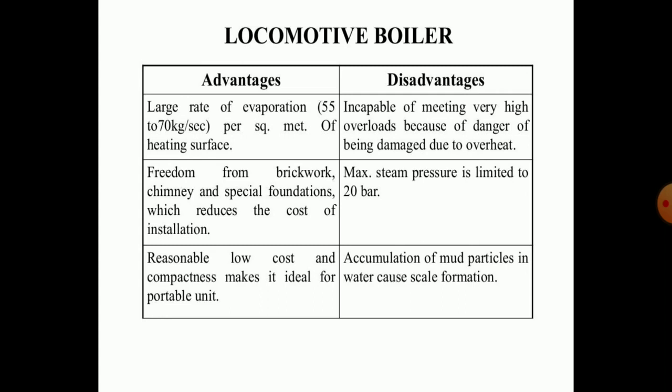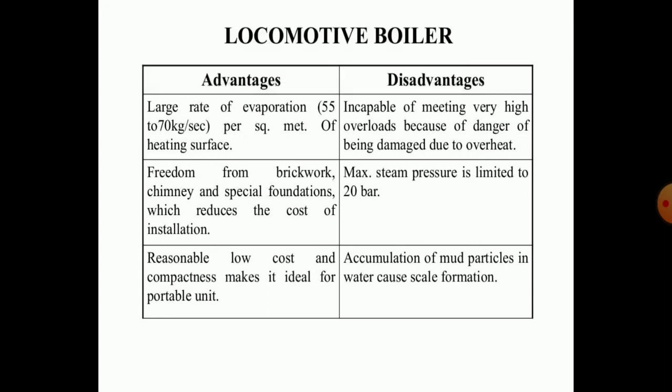Locomotive boilers have some advantages: a large rate of evaporation, freedom from brickwork and special foundation requirements, and a reasonably low cost making them ideal for portable use. However, they have some disadvantages: they are incapable of meeting very high overloads due to the danger of being damaged. Maximum steam pressure is limited to 20 bar only, and accumulation of mud particles in the water causes scale formation in the locomotive boiler.